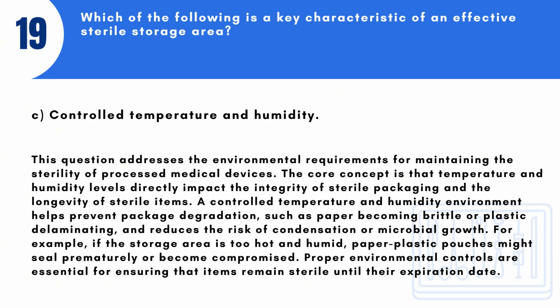This question addresses the environmental requirements for maintaining the sterility of processed medical devices. The core concept is that temperature and humidity levels directly impact the integrity of sterile packaging and the longevity of sterile items. A controlled temperature and humidity environment helps prevent package degradation, such as paper becoming brittle or plastic delaminating, and reduces the risk of condensation or microbial growth. For example, if the storage area is too hot and humid, paper plastic pouches might seal prematurely or become compromised. Proper environmental controls are essential for ensuring that items remain sterile until their expiration date.